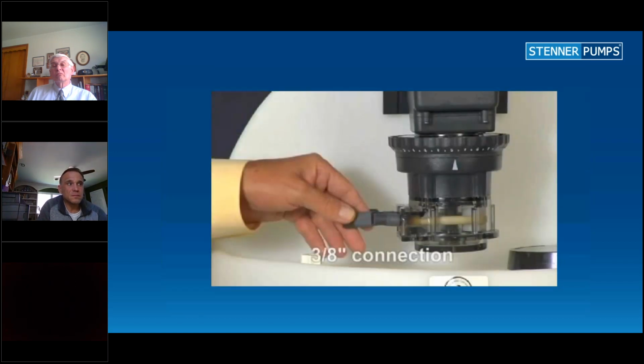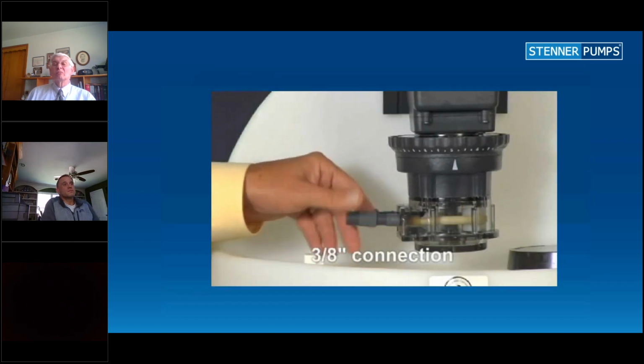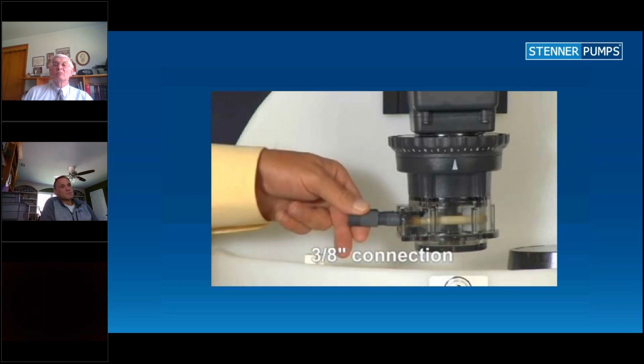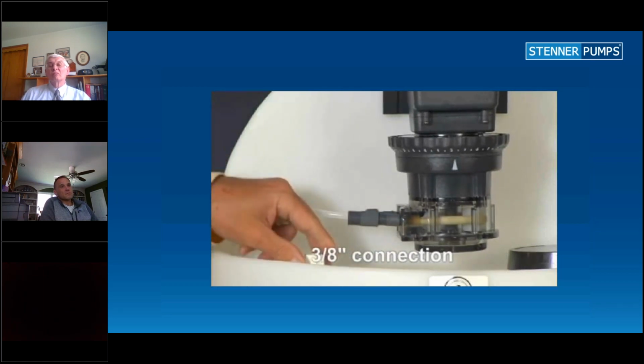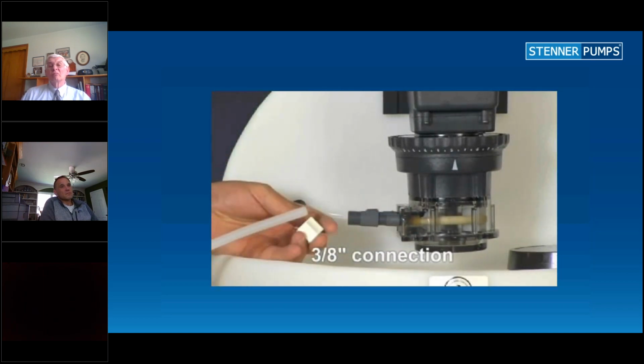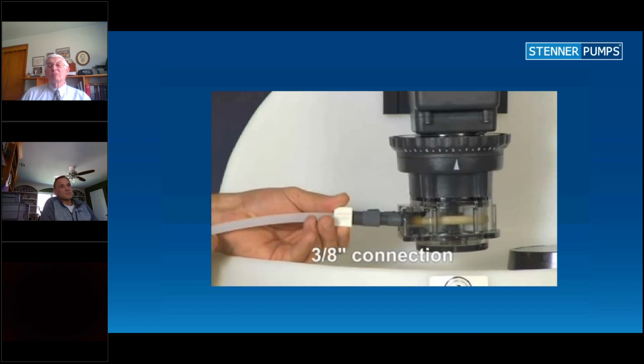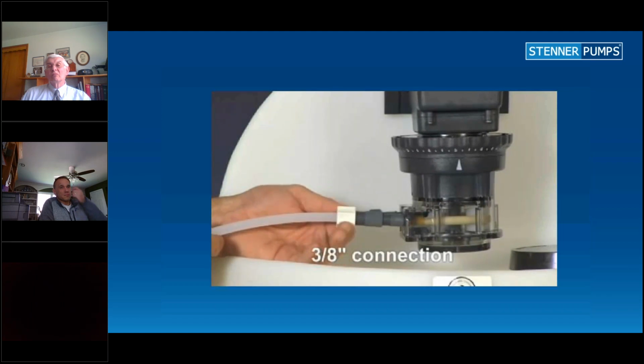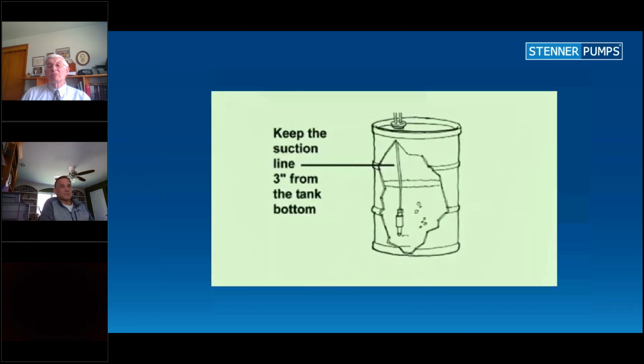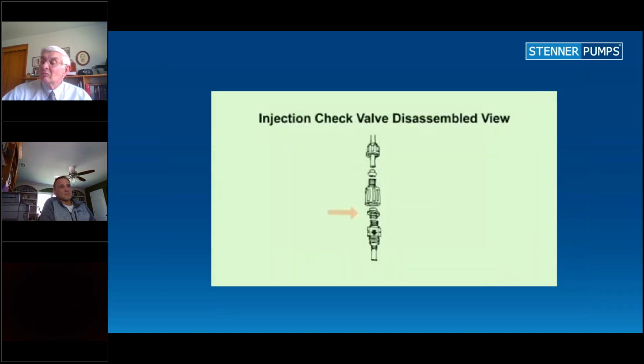If using 3/8 inch connections, keep the tube fitting stabilized and attach the female end of the adapter to the tube fitting. Slide the line through the 3/8 inch connecting nut and finger tighten to the male end of the adapter. If a leak occurs, gradually tighten the 3/8 inch connecting nut as required. The suction line should be 3 inches from the bottom of the solution tank to prevent picking up sediment. Sediment pulled through the suction line from the tank bottom can damage the pump tube and cause blockage or restriction in the check valve duckbill.